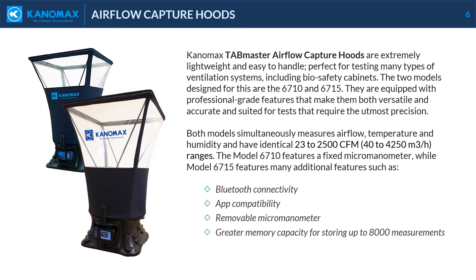Kanomax's TABmaster airflow capture hoods are extremely lightweight and easy to handle, perfect for testing many types of ventilation systems, including biosafety cabinets. The two models designed for this are the 6710 and 6715. They are equipped with professional-grade features that make them both versatile and accurate and suited for tests that require the utmost precision. Both models simultaneously measure airflow, temperature, and humidity and have identical 23 to 2500 CFM ranges. The model 6710 features a fixed micromanometer, while model 6715 features many additional features such as Bluetooth connectivity, app compatibility, removable micromanometer, and greater memory capacity for storing up to 8,000 measurements.